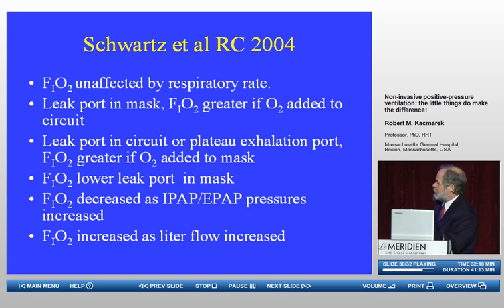FiO2 decreased as we changed the settings, or increased if you went downward on the settings. Remember, as you increase either the pressure support or the PEEP level on these devices, you increase flow. So if you have a fixed flow of oxygen coming into the system, you're going to affect the FiO2. And as you'd expect, FiO2 increased when flow increased. I put this up here to give you the extremes of what we measured.